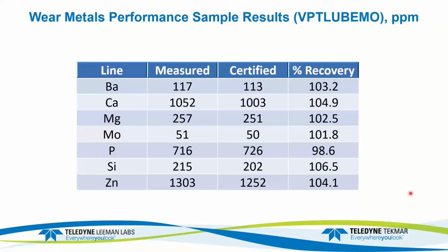What we're really trying to do is not change much during analysis. What we're trying to do is change things that waste time before the analysis and after the analysis, with the uptake and rinse. Once the instrument is running, it's running normal, except we did reduce the integration time. But again, this is a simultaneous instrument, so the peak is measured and the background correction points are measured at the same time. So even with that short integration time, all the measurements being made at the same time really keeps the precision within really tight limits.